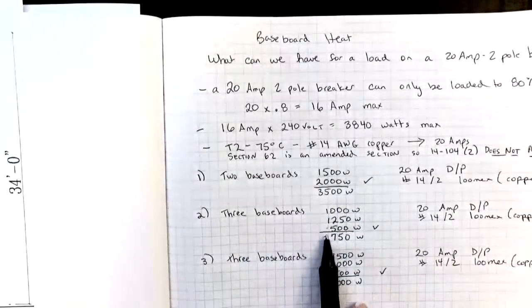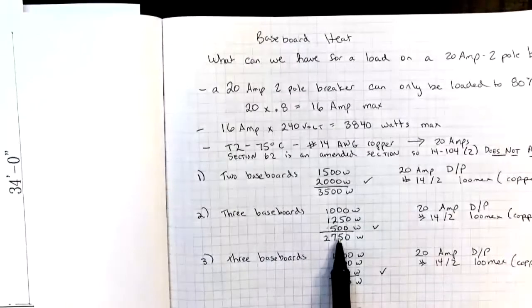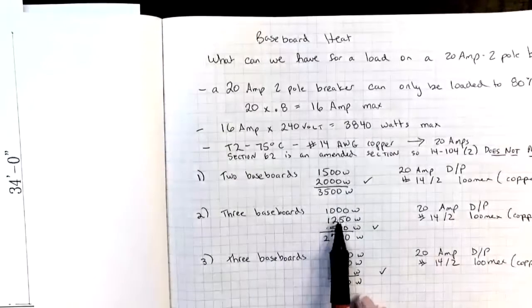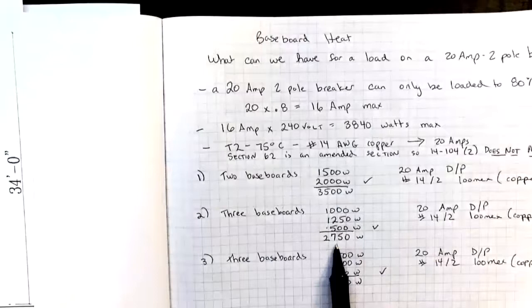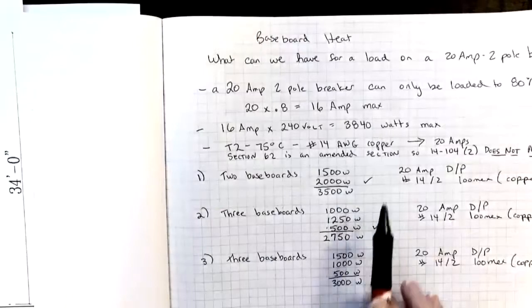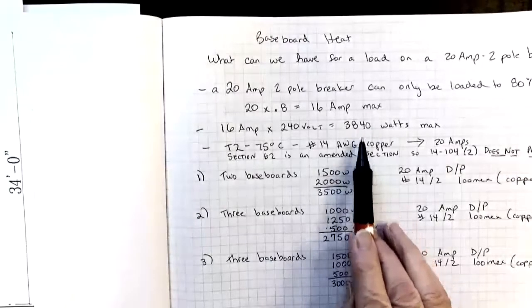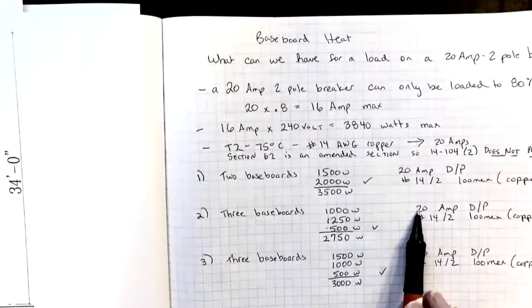I have three baseboards on this next circuit, and these are in the kitchen area in the nook. So 1000 watt, 1250, and a 500 adds up to 2750. Also fits within our maximum of 3840. So we can use 20 amp double pole breaker. And again, a 14-2 Lumex.